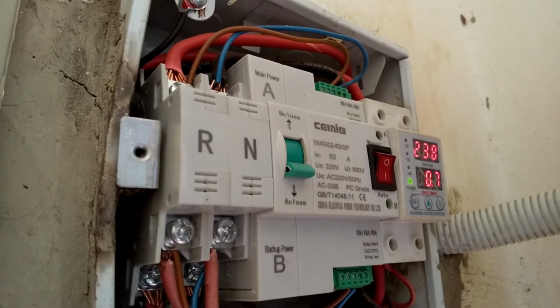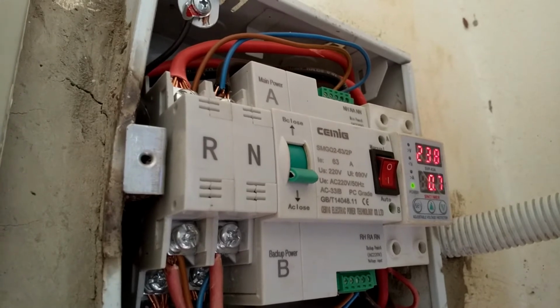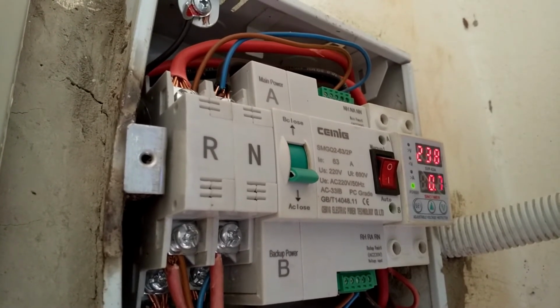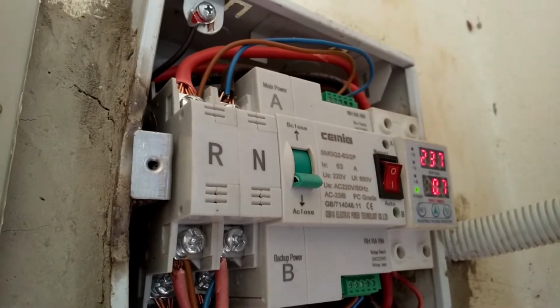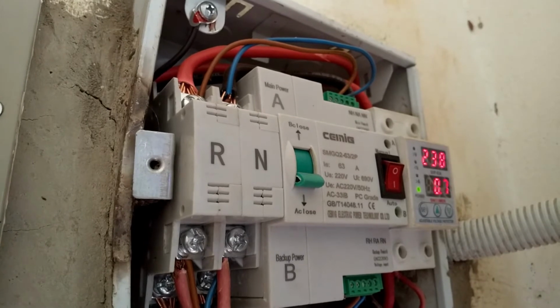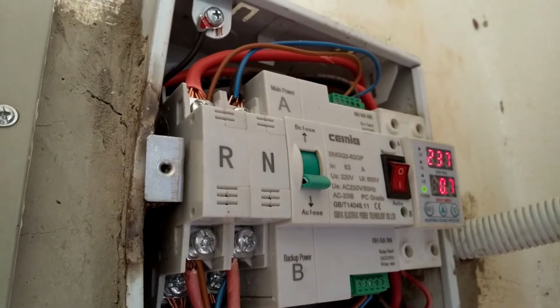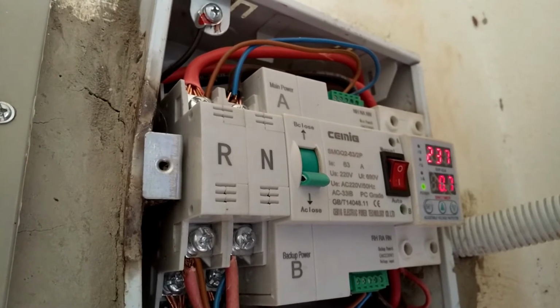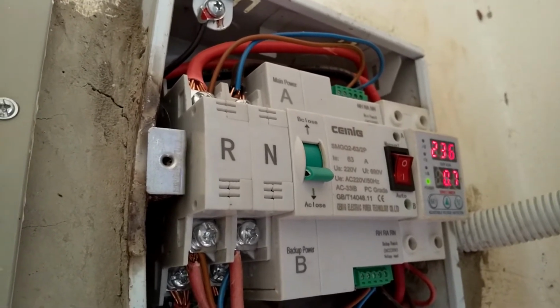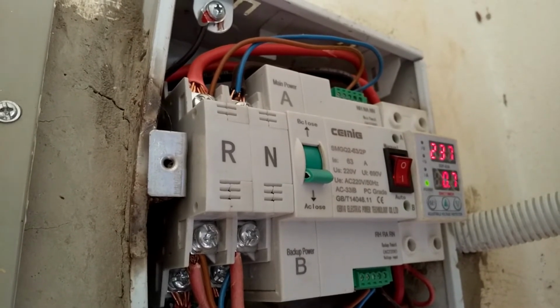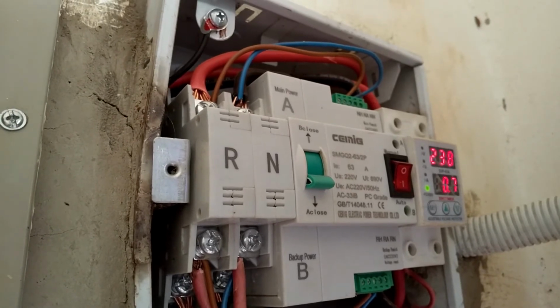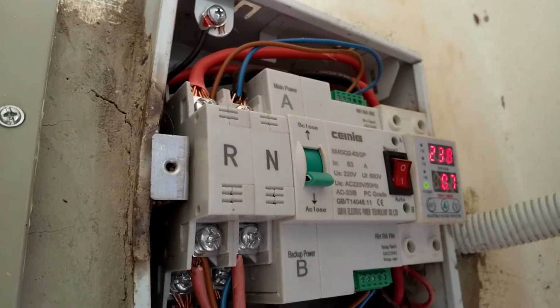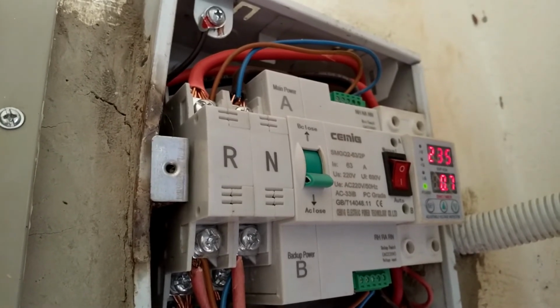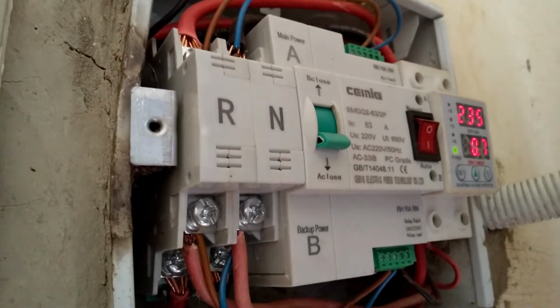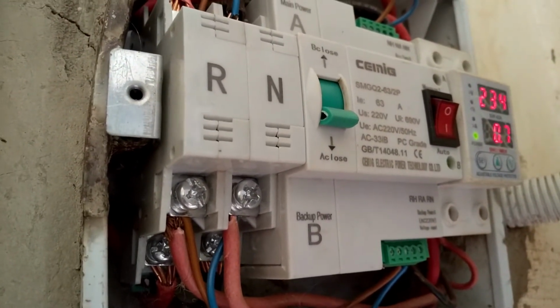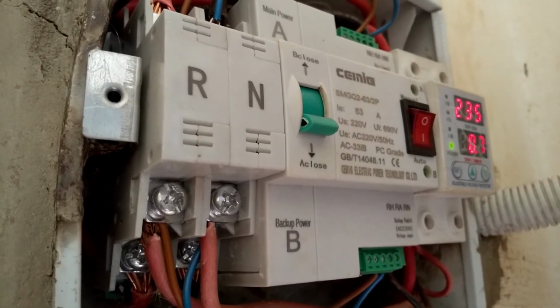And secondly, it will protect your gadgets from being burnt. Just in case the grid voltage increases, it will cut off the supply, hence protecting your installation and your equipment against damage. So I would encourage you, if you have an installation, if you're using power, you should have something that is able to protect you, especially from over voltage, because it's the one which does a lot of damage. And there are some equipment which are also very sensitive to low voltages, because they're always fluctuating and the gadget needs steady power, and you might find the gadget will also get spoiled because of low voltages. So that relay is basically for over voltage, under voltage, and with the overcurrent limiting function.